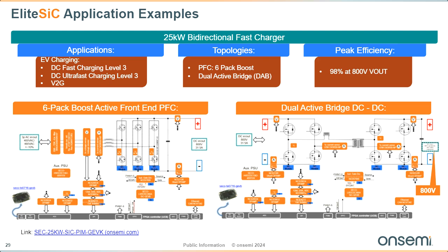Here we have a very high level block diagram of our 25 kilowatt bidirectional fast charger. This application is for DC fast charging, including level 3 and ultra fast charging level 3, and also V2G, or vehicle to grid, because it's bidirectional. So you have the 6-pack boost active front end PFC on the left and the dual active bridge DC to DC on the right. Again, it's bidirectional, and it uses a number of isolated gate drivers and silicon carbide throughout the topologies, both on the left and right side.